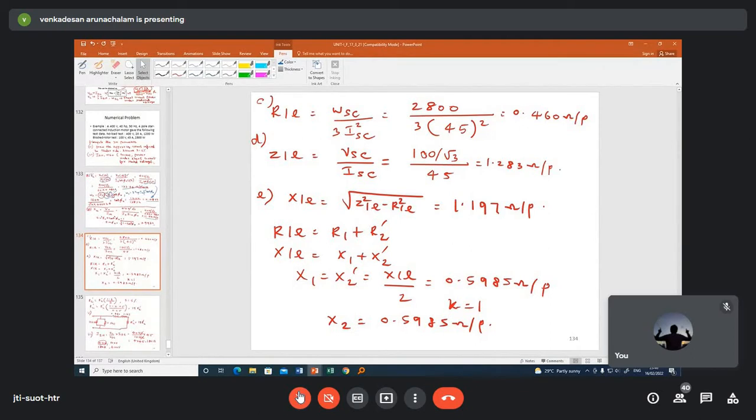And individually, if you want to calculate the resistance of stator and rotor and the reactance of stator and rotor, you can use some approximation. What approximation we are doing here is that we are taking K equal to 1 and we are assuming the stator reactance is equal to the rotor reactance. So R1E is nothing but R1 plus R2 dash, X1E is nothing but X1 plus X2 dash, and X1 is equal to X2 dash, that is X1E by 2.